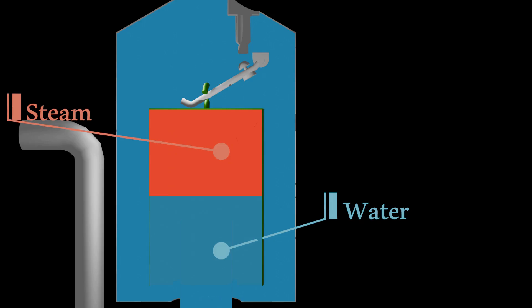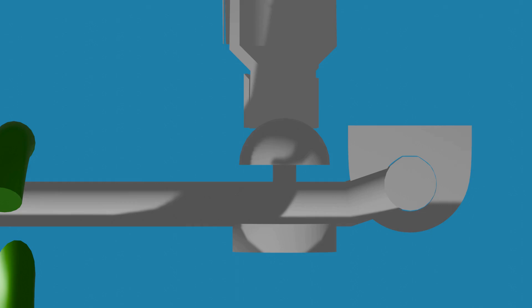When steam fills about two-thirds of the bucket, the bucket starts to rise. The reason for this is going to be discussed later in the video. When the bucket rises up, it closes the valve and no fluid exits from the trap.